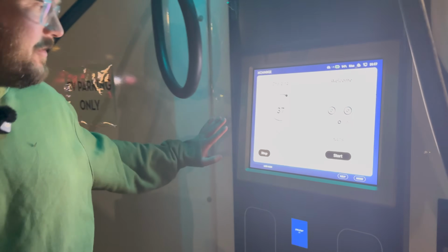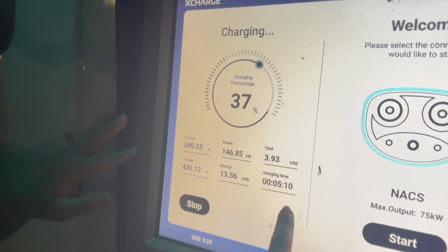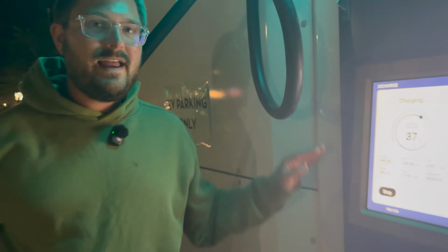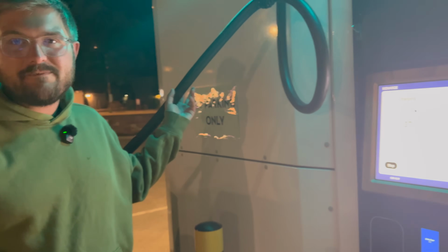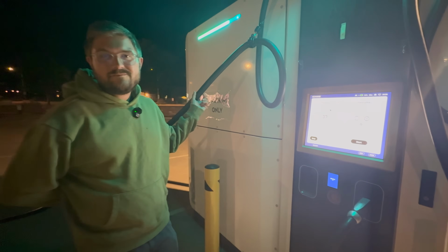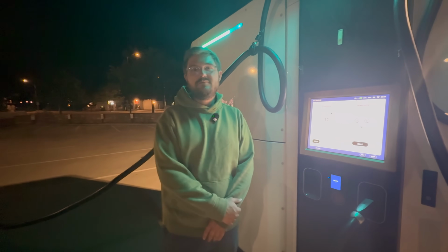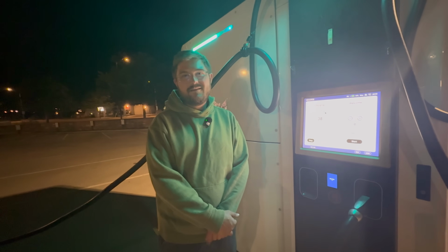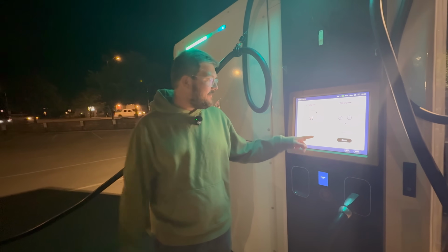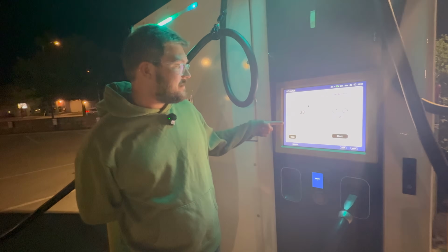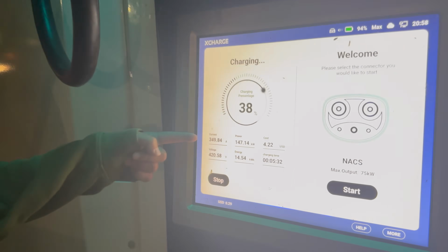Oh look, we're dipping down—yes, this is the other thing they were discussing when they were here with you. They mentioned that the boost profile, where they go 50 amps higher on the cable, was temperature based. Yes, because I asked, since you told me it was stopping at 5 minutes. I asked if we could extend that, and they said it's temperature based. Except it's always exactly 5 minutes into the charging session when we go down to the nominal rating of the cable.